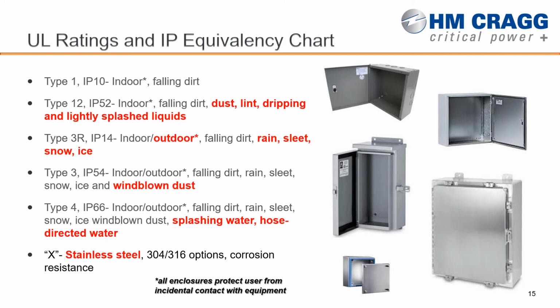Type 3R, that's your next level up. This is a true outdoor enclosure. It can be used indoor, but it can also be used outdoor because it now provides a level of protection against rain and sleet, snow, and ice. Basically the test is, as long as the water or the snow is coming down at less than a certain angle, and as long as the water is not able to permeate or get into the enclosure, then it's going to carry the type 3R rating. The next level up would be the type 4, and that one is fully sealed.